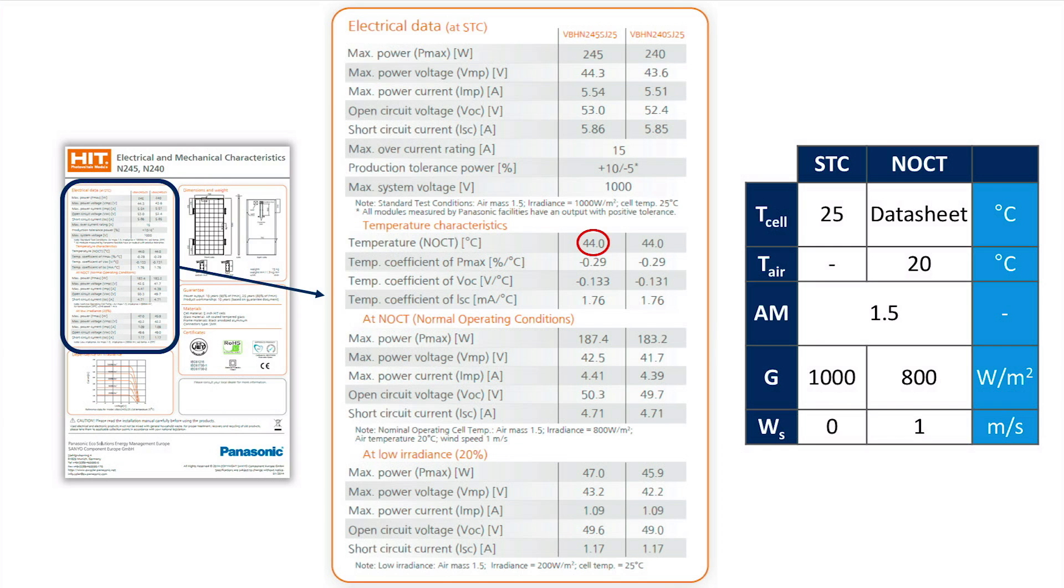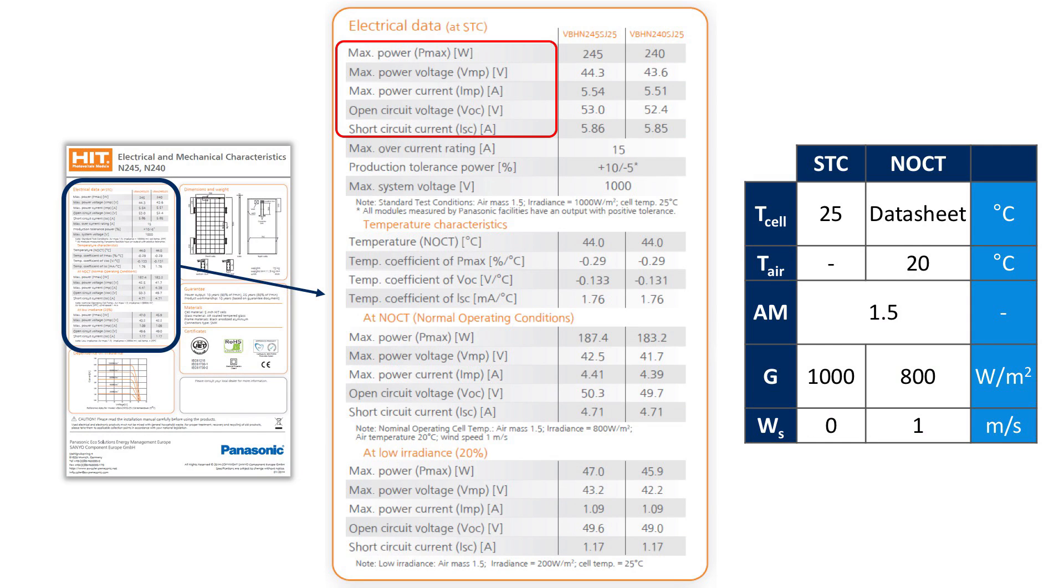Having defined both STC and NOCT, we can now focus on the electrical data which are the power, the voltage and current at the maximum power point, the open-circuit voltage and the short-circuit current. In STC case, also the maximum current and system voltage are reported for safety as well as the production tolerance power. This last parameter specifies the range within a solar cell will either overperform or underperform its rated power P at STC conditions.